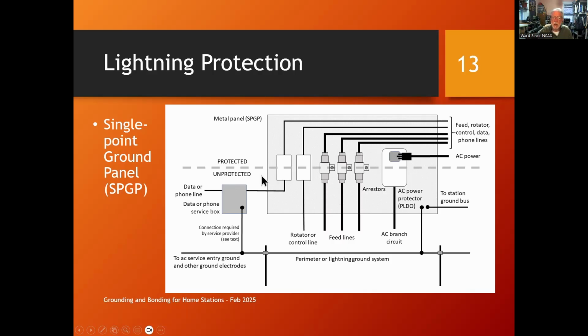So keep your unprotected cables away from your protected cables. Run them through different conduits, run them one from above and one from below or side to side. Whatever you got to do, create that big air gap between those two sets of cables.